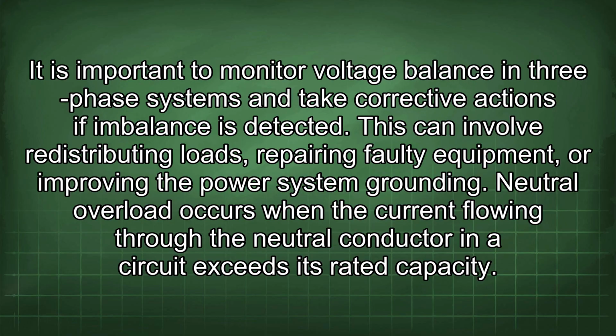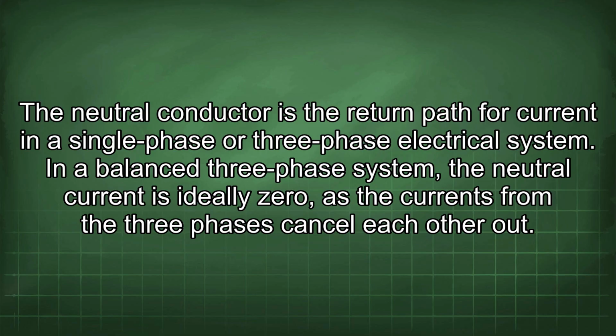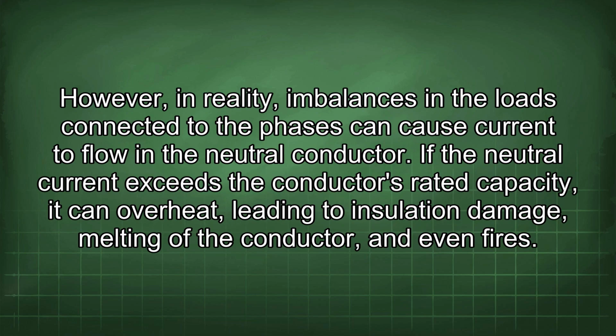Neutral overload occurs when the current flowing through the neutral conductor in a circuit exceeds its rated capacity. The neutral conductor is the return path for current in a single-phase or three-phase electrical system. In a balanced three-phase system, the neutral current is ideally zero, as the currents from the three phases cancel each other out. However, in reality, imbalances in the loads connected to the phases can cause current to flow in the neutral conductor. If the neutral current exceeds the conductor's rated capacity, it can overheat, leading to insulation damage, melting of the conductor, and even fires.